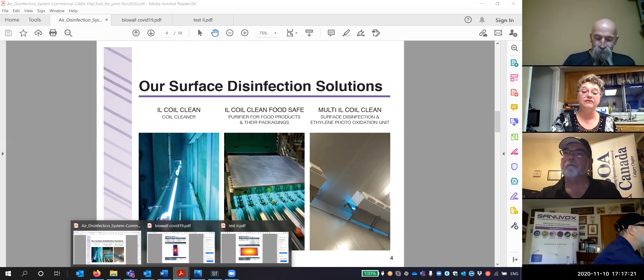Now, whenever we size out a coil clean, I basically need the size of the coil, and it doesn't matter if it's like 120 inches long or, you know, it's 6 feet high, whatever. And this is kind of an example of what you would get as a result of the calculation. What we have here is the coil size and the type, and then you have a visual of your treatment. We always want to get all 4 corners of the coil. And then also minimum dosage: engineering firms say 232 microwatts per centimeter squared is the minimum.